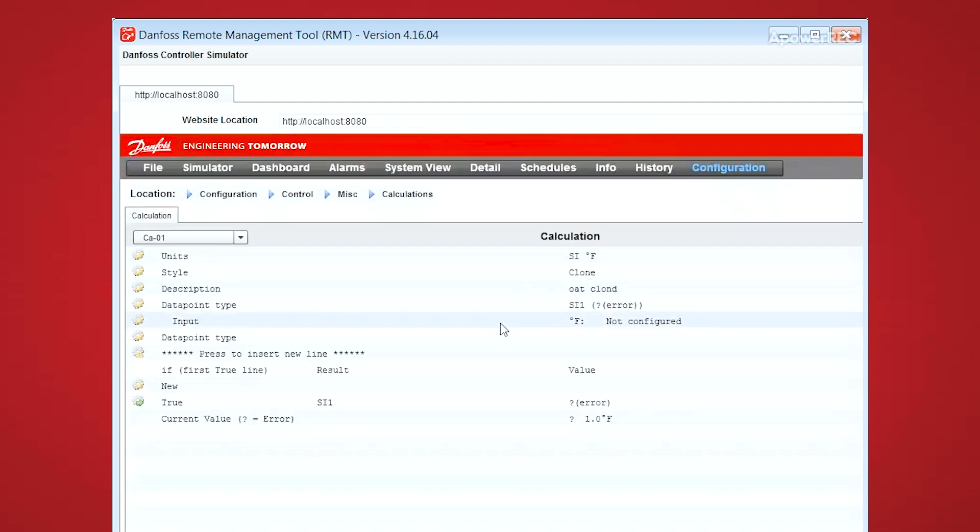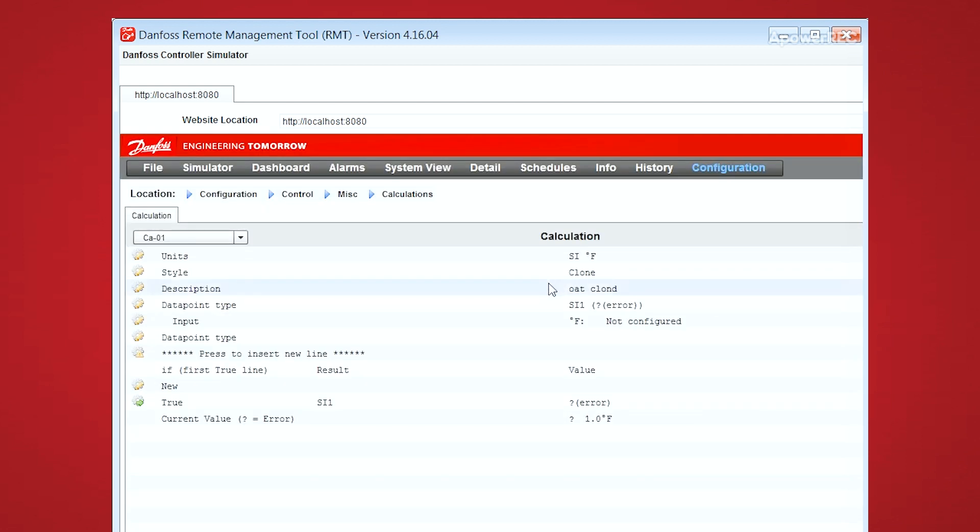From here, we choose the input sensor that we want to clone, in this case the outside temperature. And then you can see down in the output, the first logic statement is a true type, which means that we'll always evaluate as true, and therefore we output that particular result.